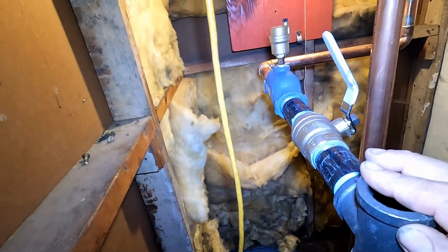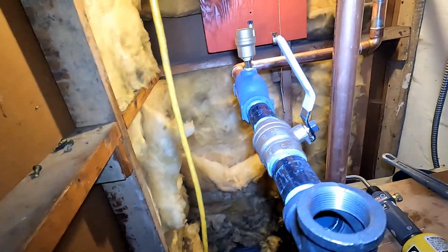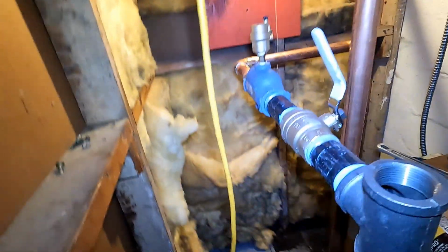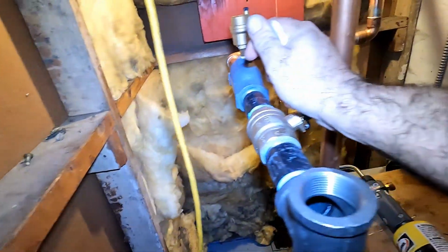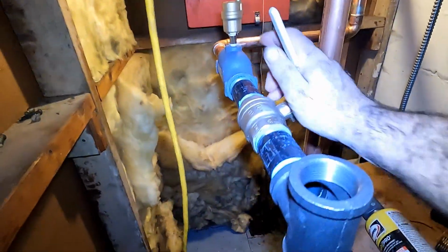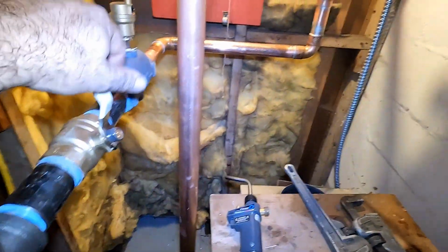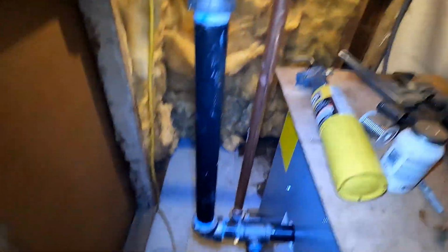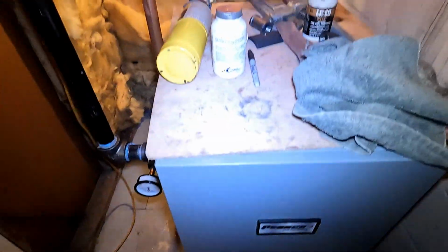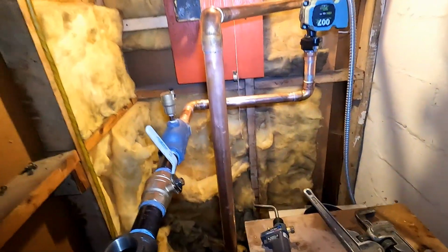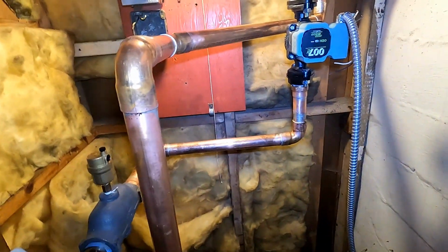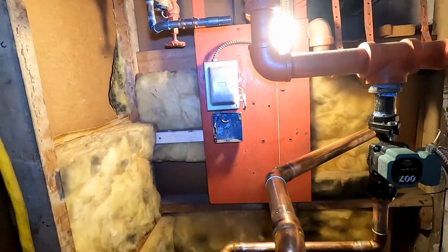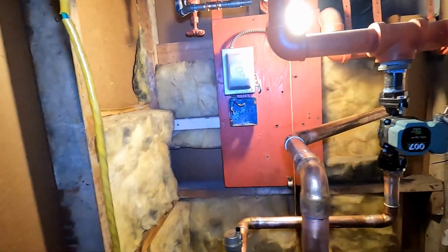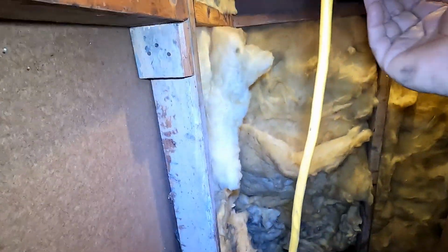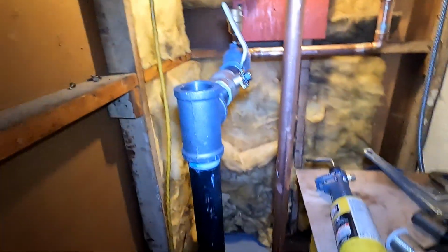So we're going to put a bushing here and a boiler drain. This valve is going to just shut off. We don't need isolation. This is a small house. This is to stop the water from going in the supply and push all the air out. So this is the same as the Dunkirk. We have the circulator pumping away. We're going to put a new feed valve up there. It's going to connect down in here with a T in the compression tank.